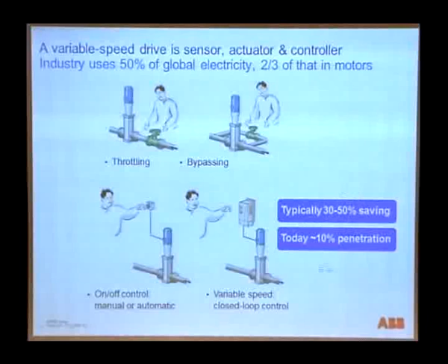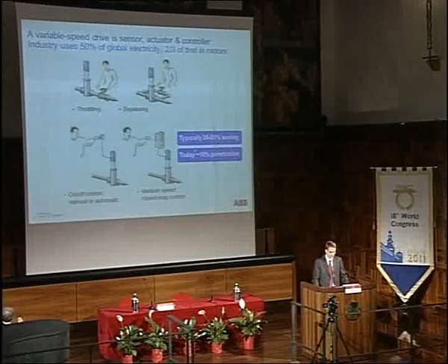But with variable speed drives, you move this to closed loop control, bringing it to just the speed you actually need for the process, which normally comes with something like 30 to 50% savings on the energy side, as well as better quality and reliability of the product and process plant. Today there's about 10% penetration. If you do the math, 50% of global electricity is consumed in industry, two-thirds of that in motors. And if you look at today's already 10% penetration, you can say drives, and the control in those drives, are already making a very sizable contribution.